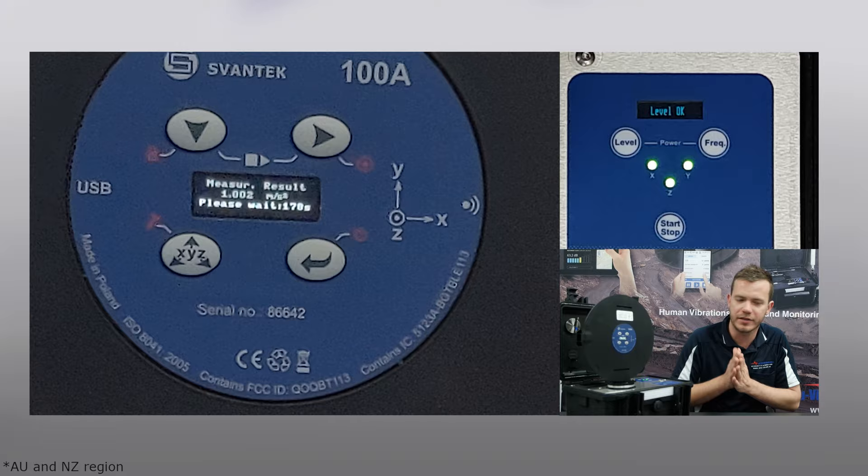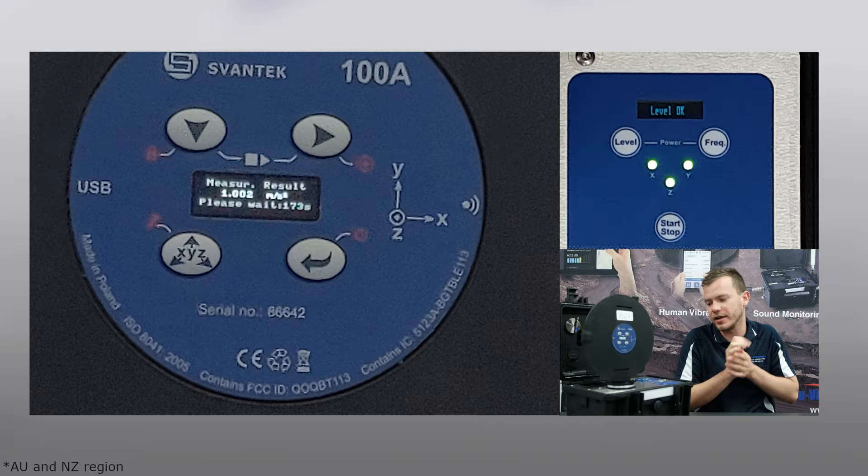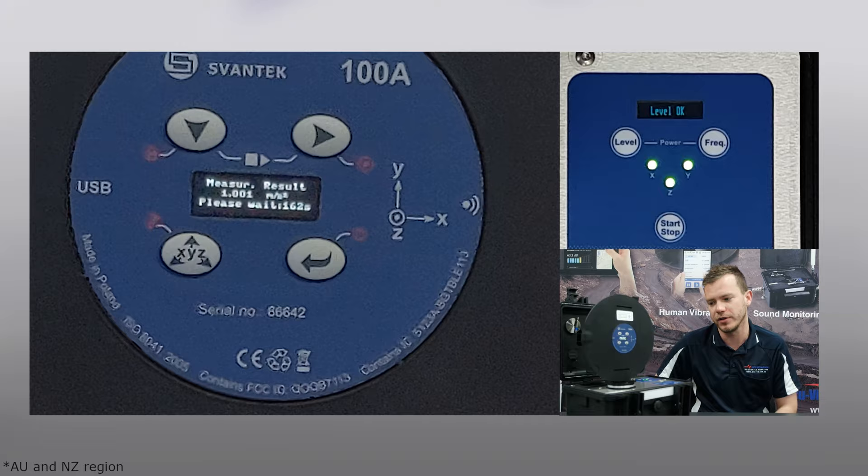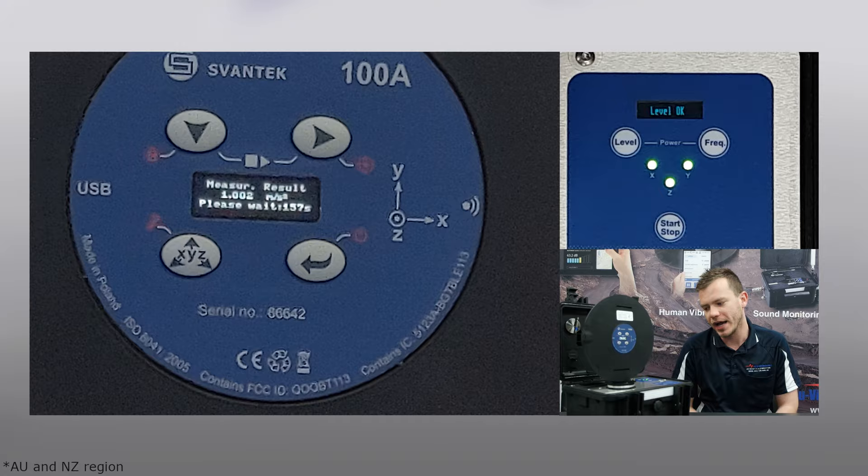We're going to wait for 174 seconds and then we should see a result. This is before and after a measurement. Typically if you're using this, you're the best in your game. This is what it's all about - before and after measurements, verifying that the whole body or hand arm transducer hasn't been affected during the day's work.